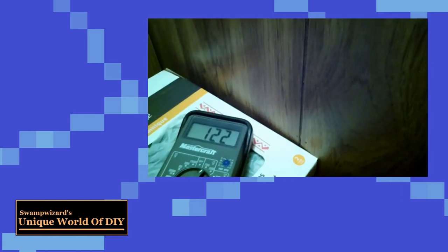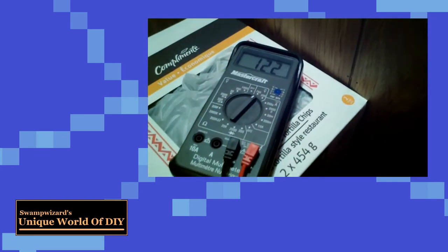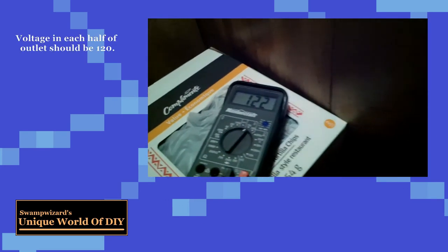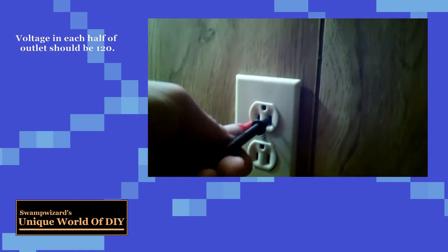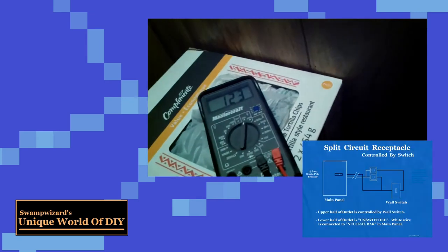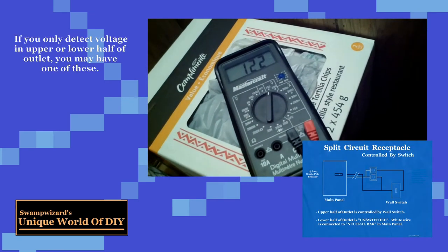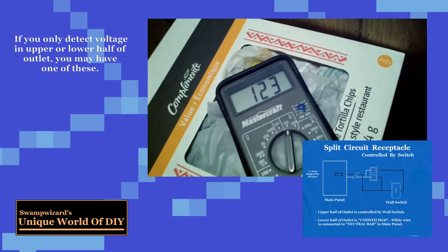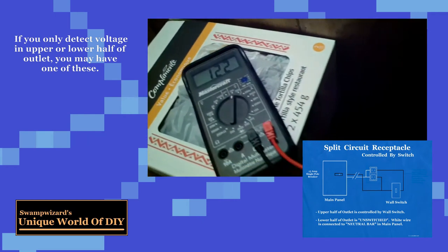From time to time, you may run into another type of split circuit outlet too, where the top half of the outlet or the bottom half of the outlet is controlled by a switch. Now, these are usually found in living rooms or maybe even in bedrooms, and they're usually used to control a table lamp from a wall switch. They're not 240 volts, these will be 120 volts. They're usually wired to a single 15 amp breaker in the main service panel.